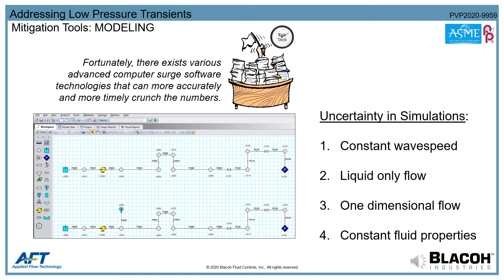It is important to understand key assumptions and simplifications that even computer software calculations take into account. The two primary factors attributing to some uncertainty are constant wave speed and liquid-only flow. To some extent, there is always a degree of air entrainment within a fluid, which can lower the wave speed. When a system is experiencing cavitation, it is most certainly in two phases — liquid and gas.